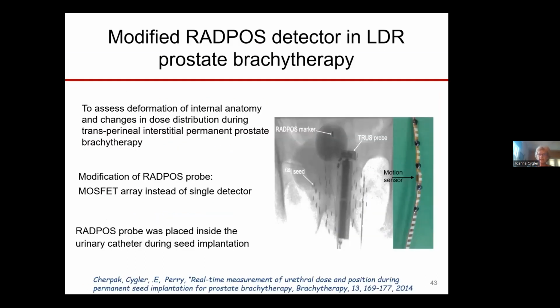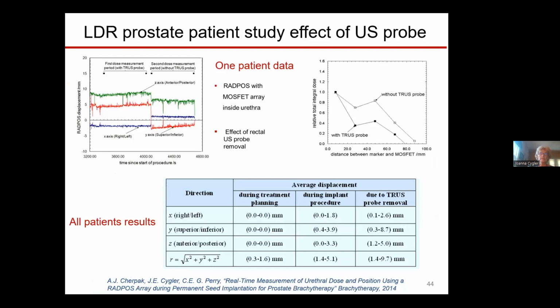So in LDR prostate brachytherapy, we use a modified RADPOS detector to measure dose and prostate deformation caused by the insertion and then removal of the transrectal ultrasound probe. In this modified probe, we actually used 5 MOSFET detectors, an array, instead of a single detector. And we placed it in the urinary catheter, and that went into the bladder. And here at this point, if you can see, there is a special radio-opaque marker that indicates the end of the RADPOS probe. And I will show you some results of the measurements now.